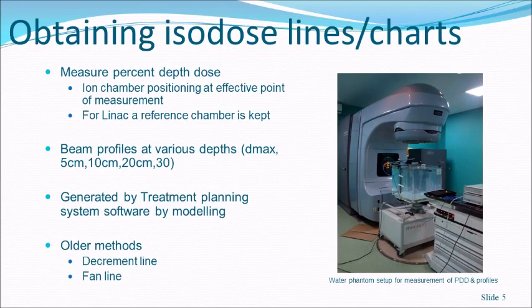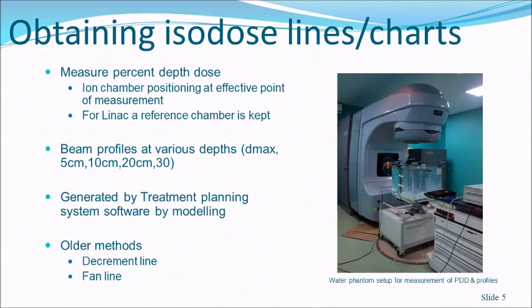For obtaining isodose lines and charts, you need a water phantom in which an ion chamber can be moved in x, y, and z directions remotely for measurement of depth dose and beam profiles. A reference ion chamber is also required. For LINAC, the ratio of the measurement chamber to the reference chamber is plotted for depth dose and beam profiles. Beam profiles should be measured at D-max, 5, 10, 20, and 30 centimeters. Present-day treatment planning systems use these data to model the dose distribution.